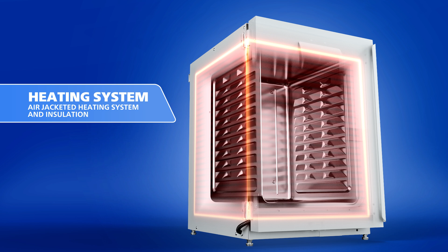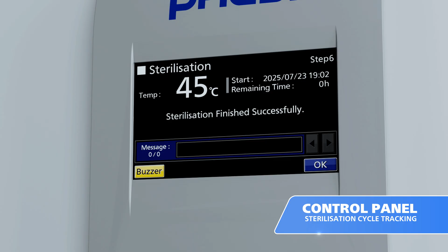The new insulation offers higher resistance to help retain heat during normal operation and reduce heat leakage during high heat sterilization. The control panel tracks sterilization cycles, ensuring the incubator remains in proper working order throughout its lifespan.